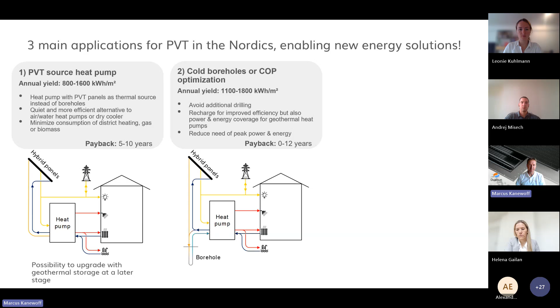Another application is existing borehole storages that have gotten cold. And that happens over time if you increase the heat pump capacity without extending the storage system. Or if we have high-profile projects where we need to improve the heat pump COP throughout the year with solar energy. And the third option is to optimize geoenergy storage, or as we say, to enable more geothermal energy systems in Europe.